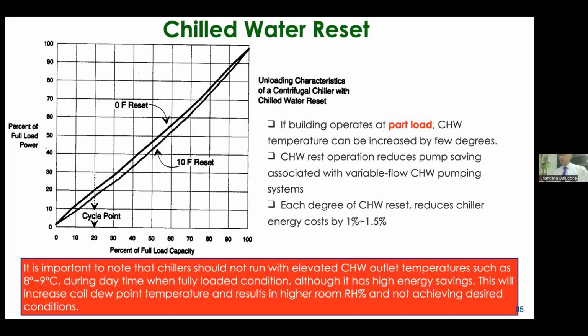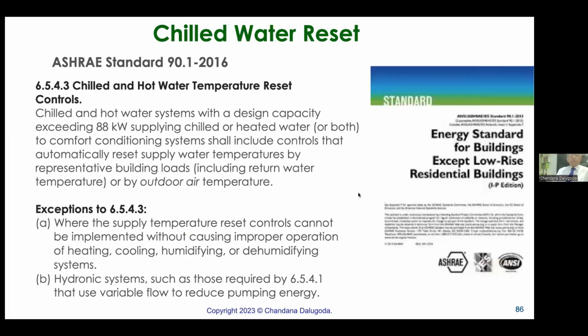We can't use this during peak time. So what will happen? You can't bring the environment to the comfort zone. Relative humidity will increase, condensation will occur. So high RH is not what we require. So it is used only in part load conditions. Now that is in ASHRAE standard 90.1. Any chiller exceeding 88 kilowatts should have this function.